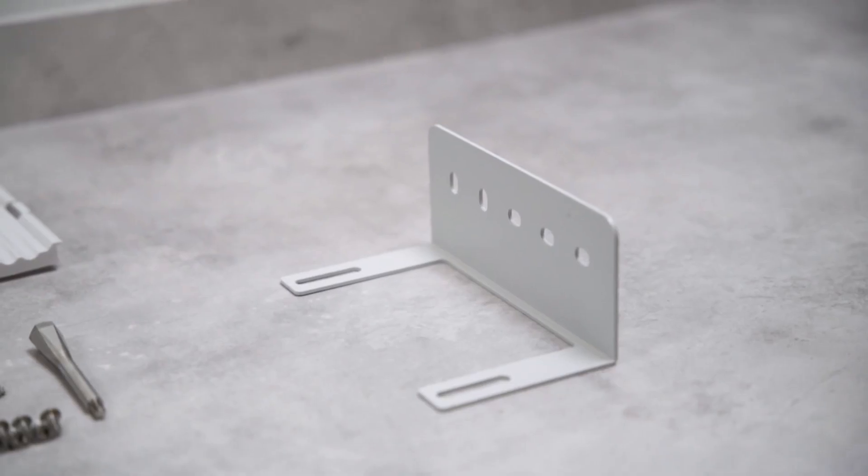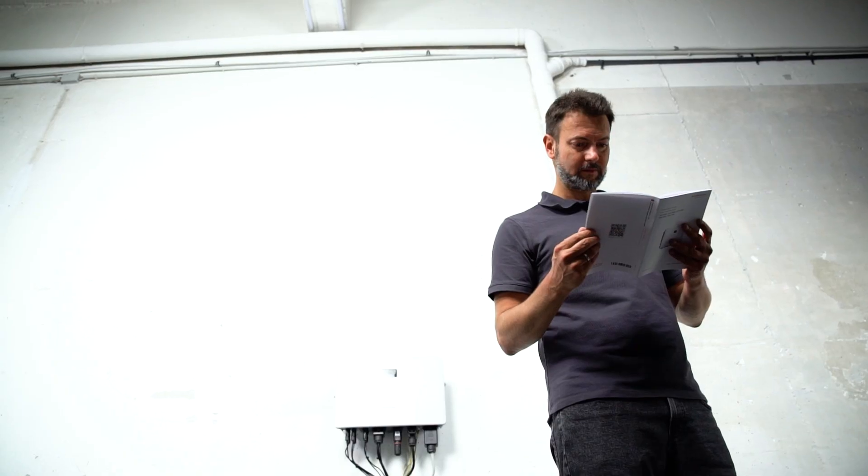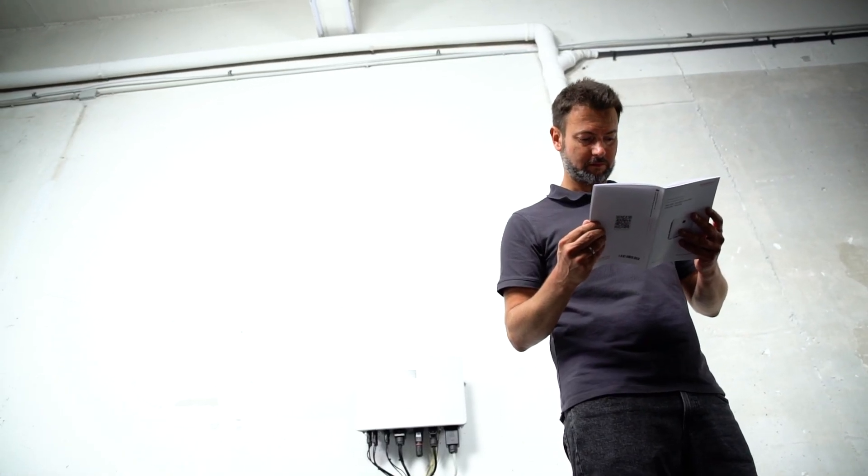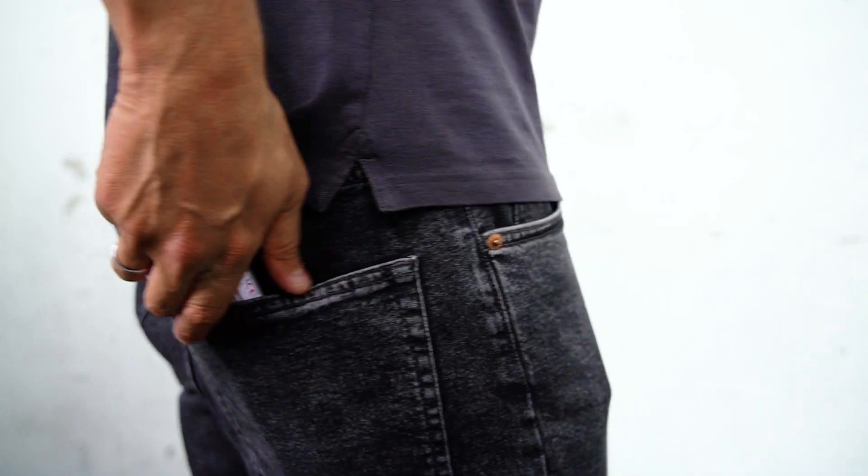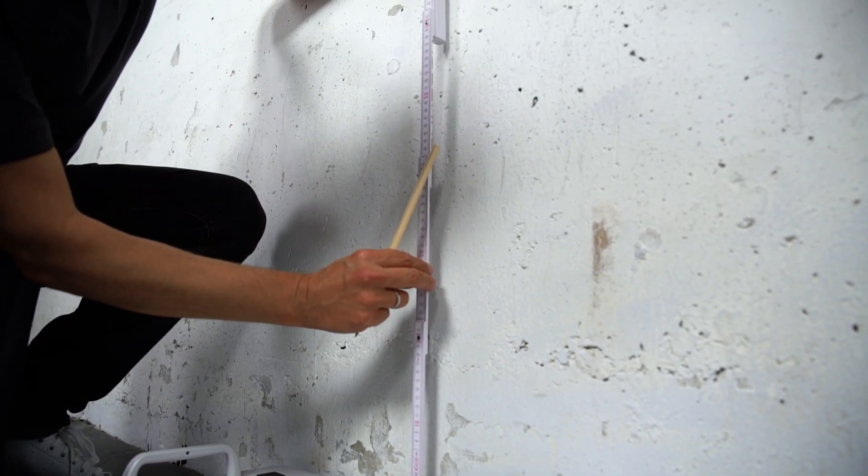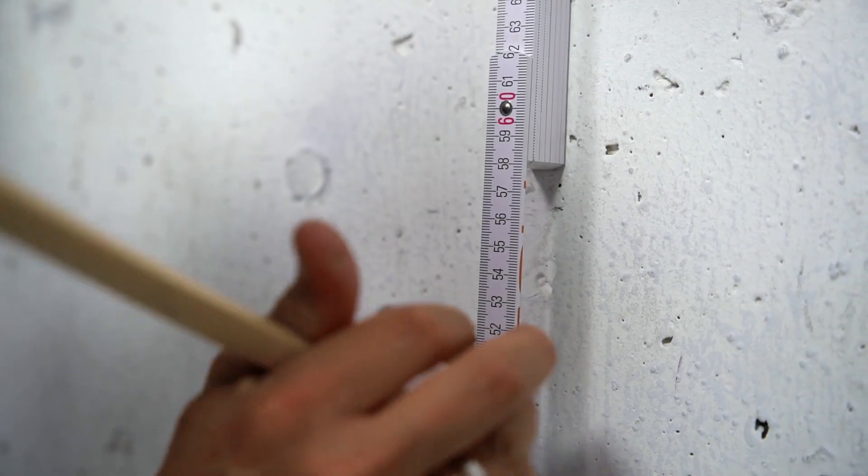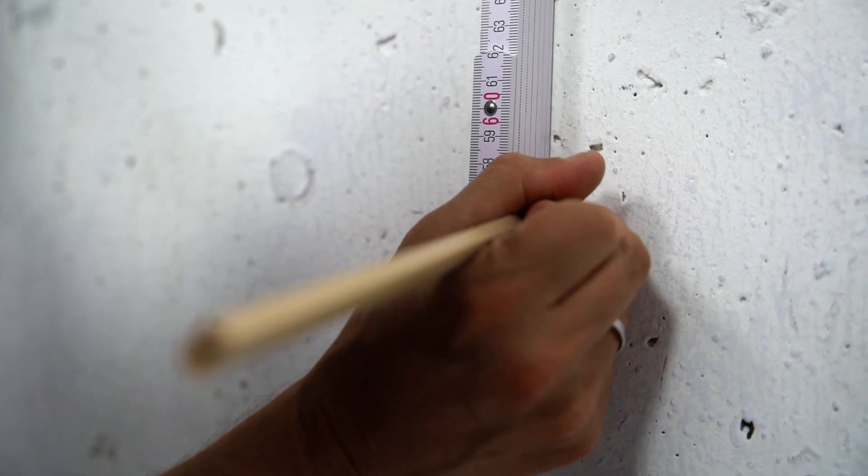The battery has to be fixed to the wall with the wall mounting plate. Check the user manual to find out on which height to place the holes for the wall bracket, which is needed to fix the battery to the wall. Measuring starts from the base of the battery, not on the floor. The height depends on the number of modules you are planning to use.